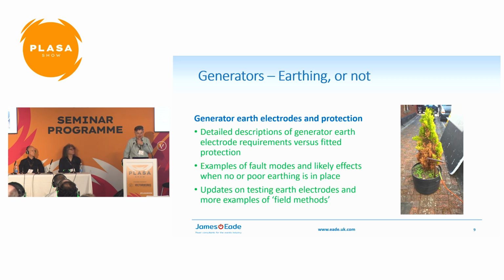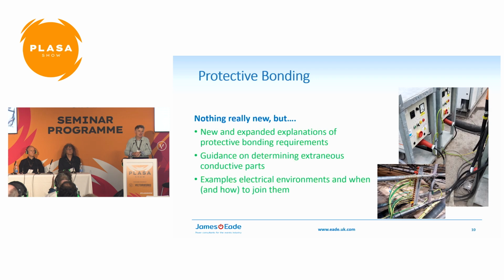The testing of electrodes, there's the classic three-pole method where you put in your current probe and your voltage probe and check the electrode under test. There's some rough and ready methods you can use by using parallel or two electrodes and a continuity test of things to make it more accessible and easier to do in the field. They're included in the guide as well, because the electrode testing equipment is not always available to everyone.